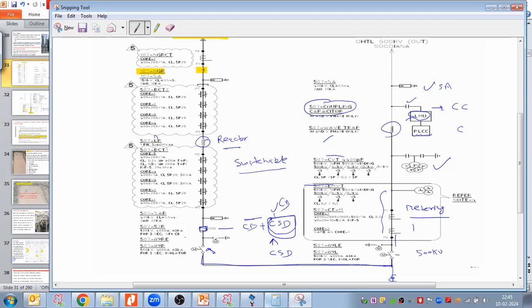And then after that we have to do the protection of this reactor. Due to that reason, we are using this surge arrester here. And this is my reactor bushing current transformer. It is indicated as a bushing current transformer, which is utilized with the reactor bushings to get the protection of this reactor. For the reactor, we require the differential, overall differential, and overcurrent and earth fault protections as backup. So all the protections will be obtained with the help of this CT, which is connected with the reactor. And then here this reactor part is finished.